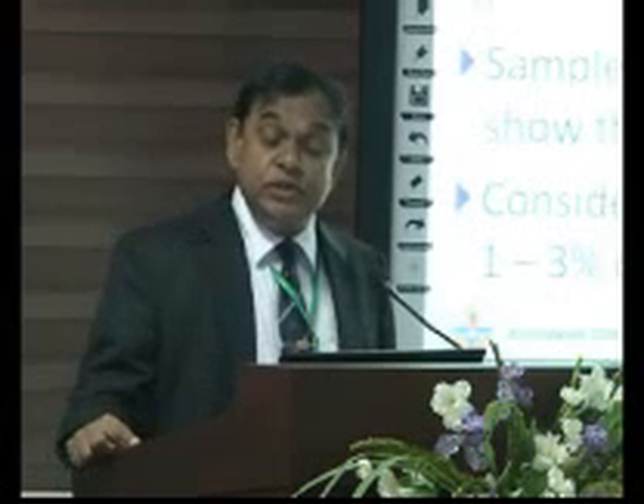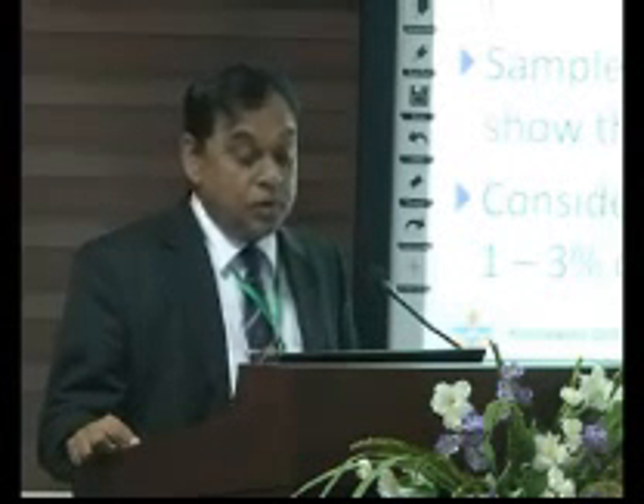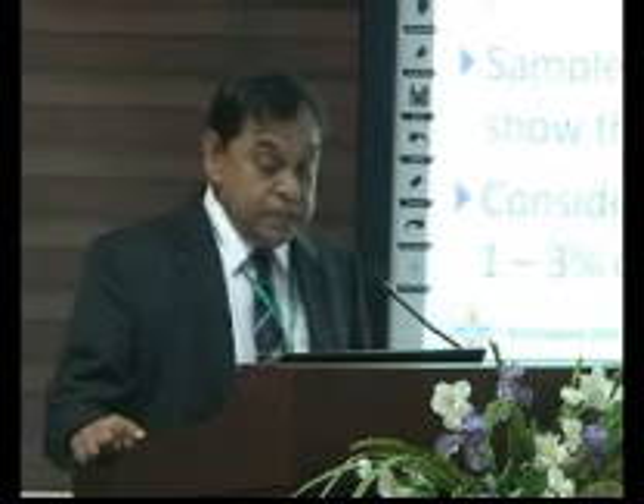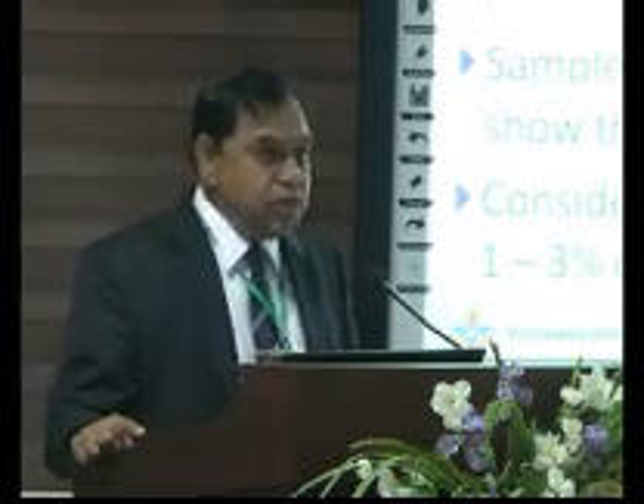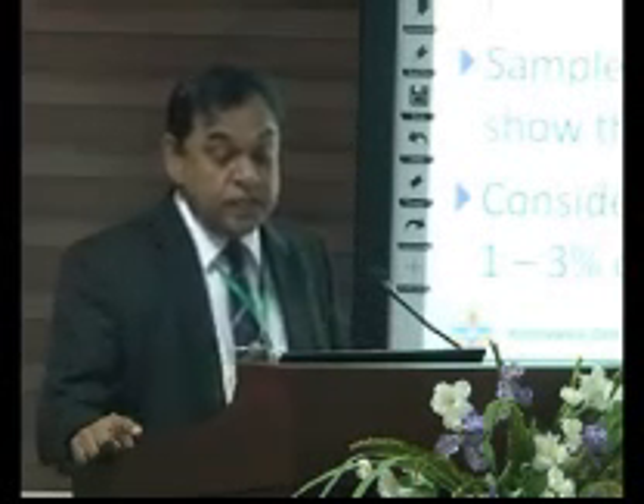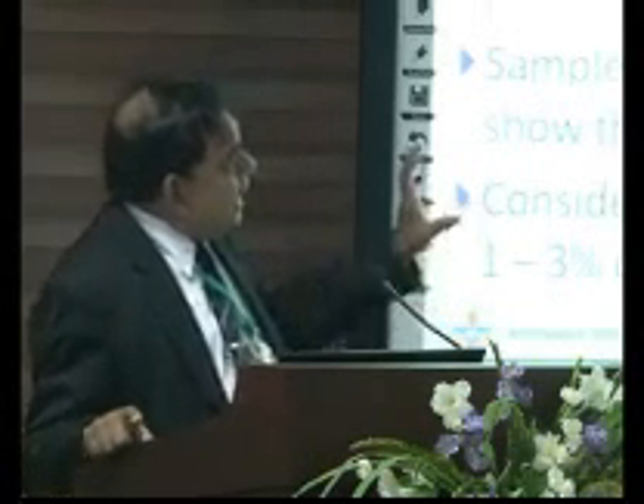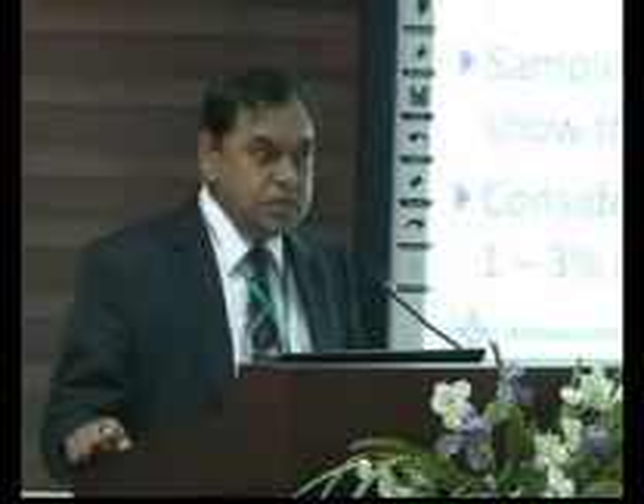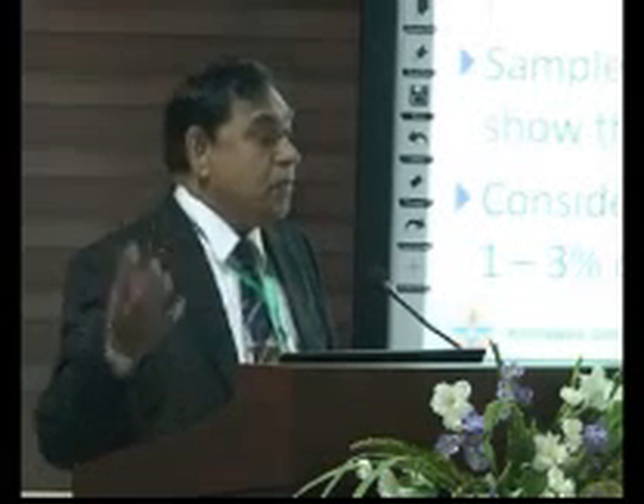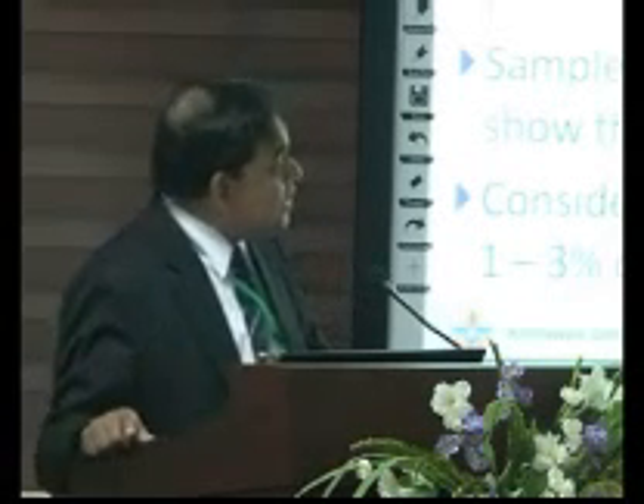Just to conclude, the potential to generate more energy from the existing hydropower plants by running them at the most efficient operating point is there and not properly utilized up to now, unfortunately. Sample calculations done for Canyon show that savings can be as high as 4.1%. I have to mention that Canyon power plant is a special case where the saving potential is higher than average. If you go to some other power plant, we will not be able to achieve the same percentage of 4.1.